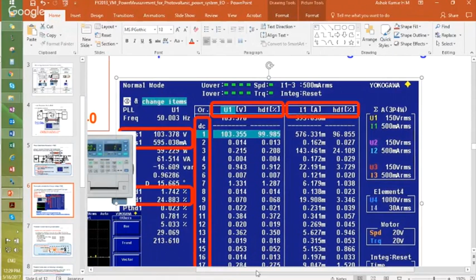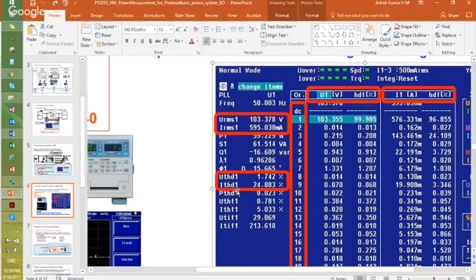If you see the harmonics, this is the voltage total harmonic and current total harmonics. Obviously we can see the current harmonic distortion is almost 24.88%, and the voltage harmonic distortion is 1.74%. We are talking about the input section. This is how we can analyze the individual harmonics as well as the total harmonics of any particular power system.